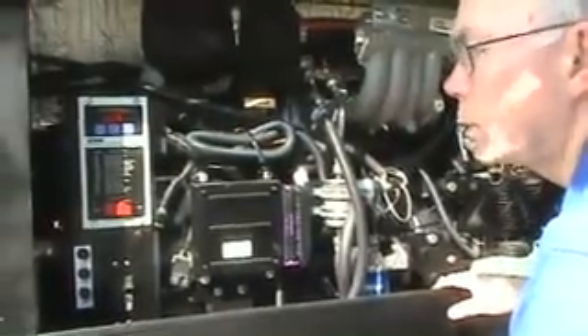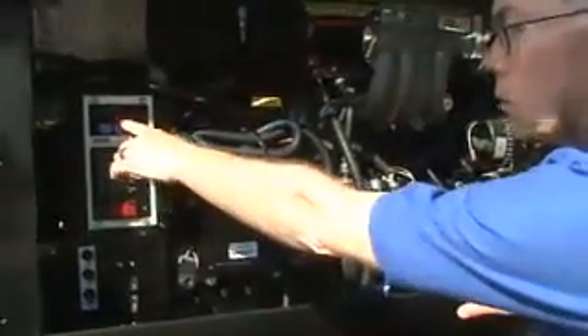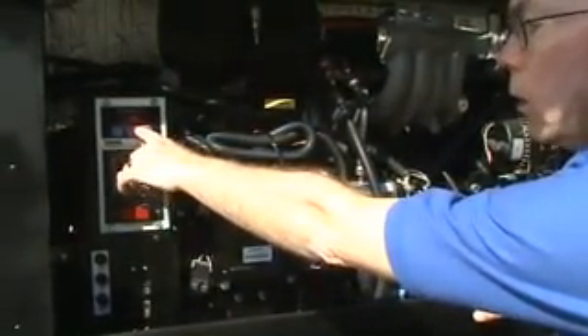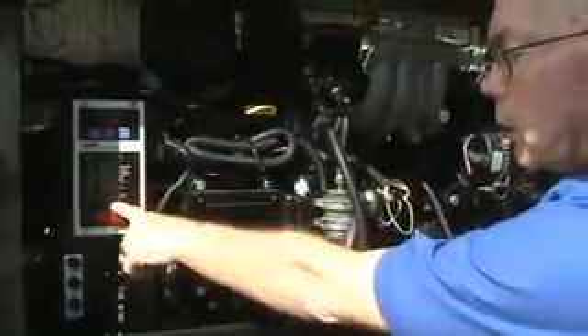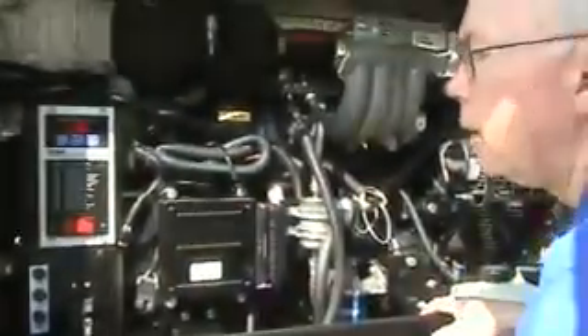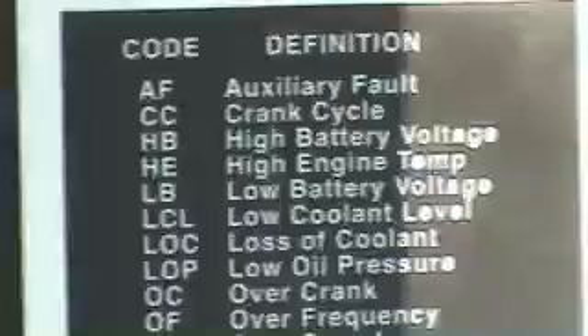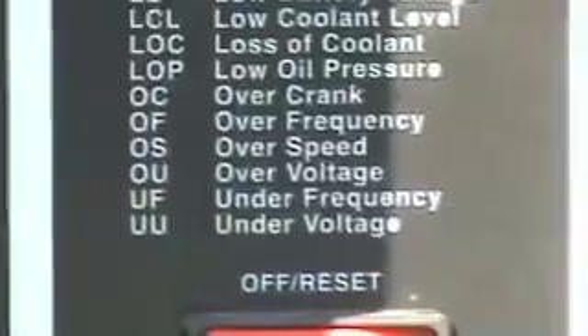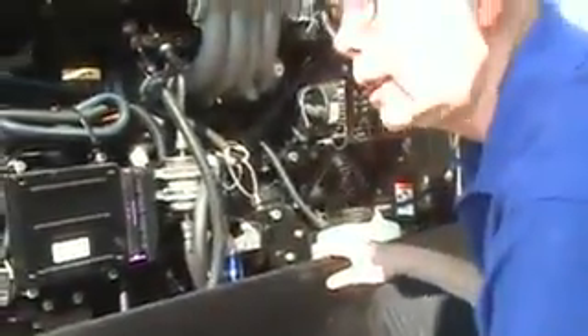Should you have a malfunction, this readout will change to an error code. You'll see some of the error codes listed here. You might be on the phone with Kohler, or with somebody at Farber, and if you're having a malfunction, you might be able to figure it out. It might be as simple as low coolant, an LCL displaying up there. Looking at your coolant recovery tank, you'll notice the low coolant level. Check for leaks—if you don't see any, just add coolant and you're back in business.